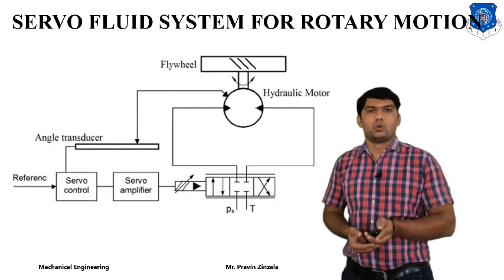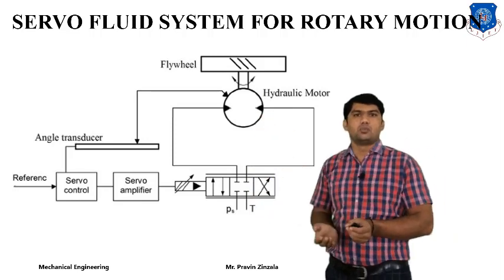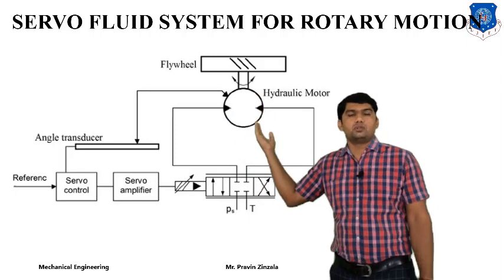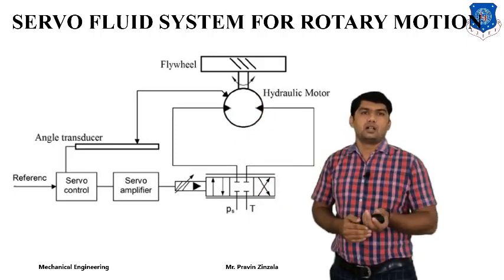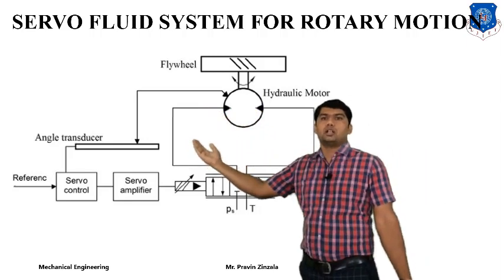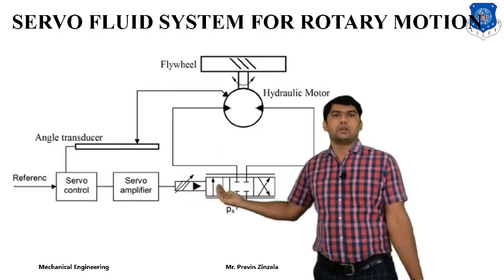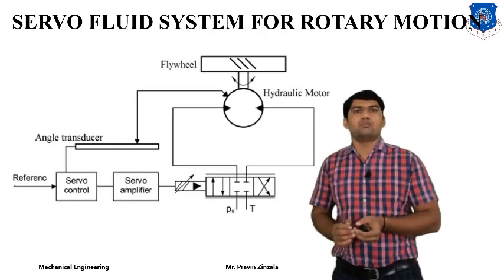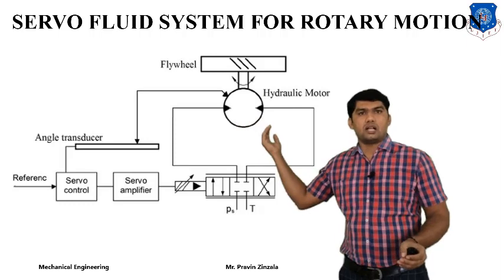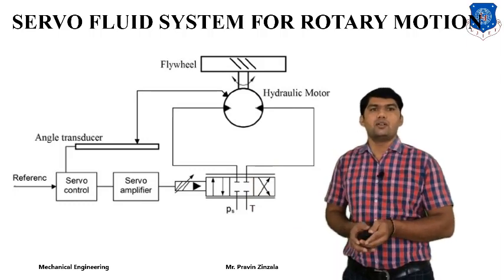A second example is a servo fluid system for rotary motion, using a 4/3 direction control valve and a bi-directional hydraulic motor. When pressurized fluid is supplied in the first position, the motor starts rotating. To achieve the required rotation speed and torque, a signal is passed from the motor to the transducer and from the transducer to the servo controller. The servo controller supplies the signal to the servo amplifier, and the amplifier supplies it to the direction control valve. According to the requirement or precise value, the valve changes position to change the hydraulic motor RPM or torque.